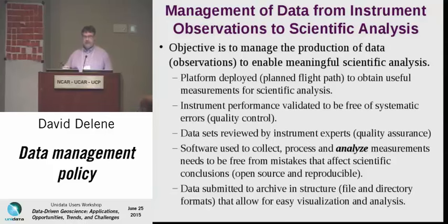The other thing that we do a lot of when we're taking this data is what I call quality control. And this is to ensure the instruments are performing as expected. That's my definition. We do tests of the instruments to make sure that there are no leaks in the instruments, that we're getting them to size correctly. This is not just seeing if they've got power. This is doing specific checks, typically every week, that the instruments are performing correctly.